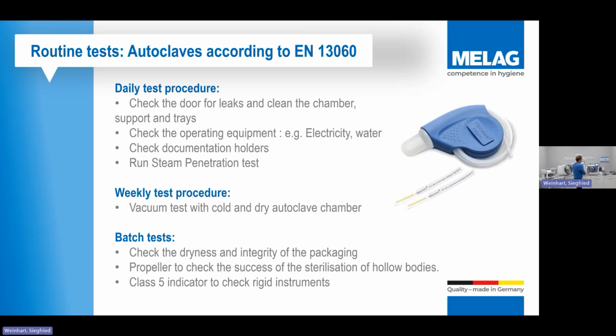Okay. If it's failed, it could well be that the door gasket needs changing. So check the door gasket first of all. If the door gasket does need changing, then let the unit cool down, run it again. Chances are it'll probably pass. If the door gasket is in good order, it's worth getting an engineer out to have a look at it, just to double check. And then we have the helix, which I'll come on to in just 2 seconds.